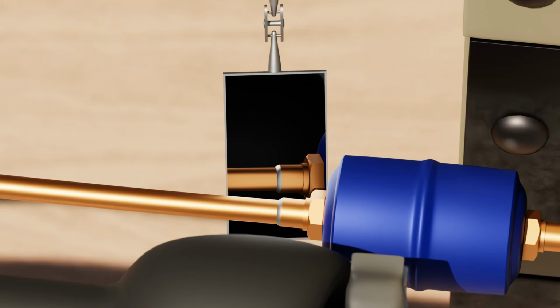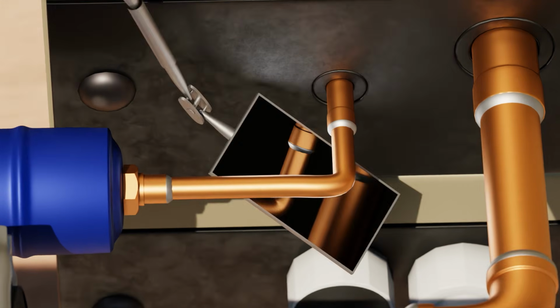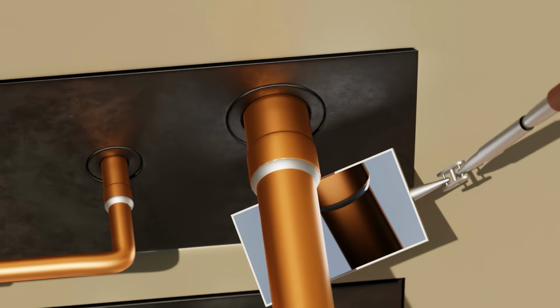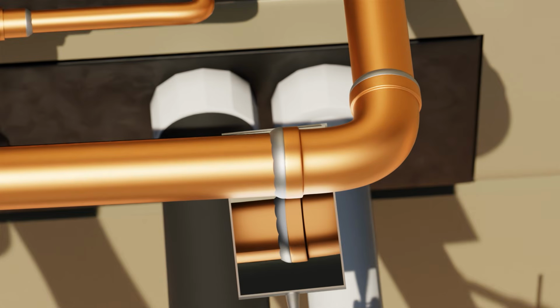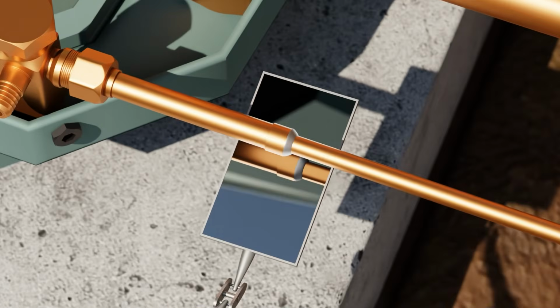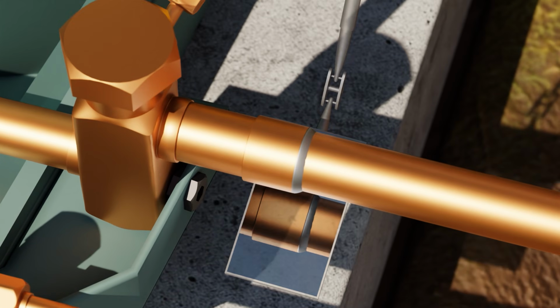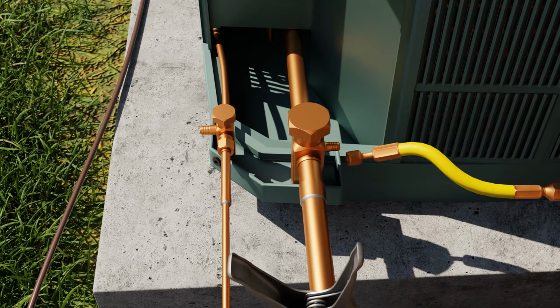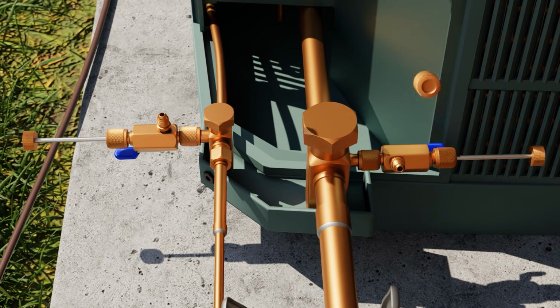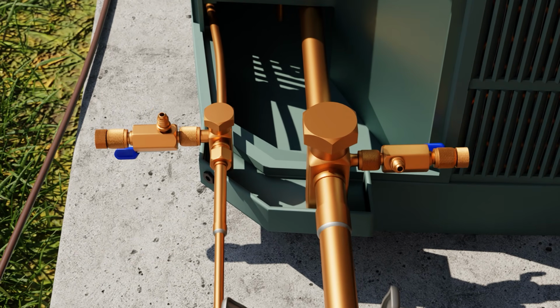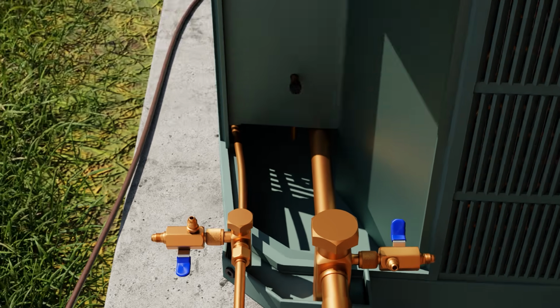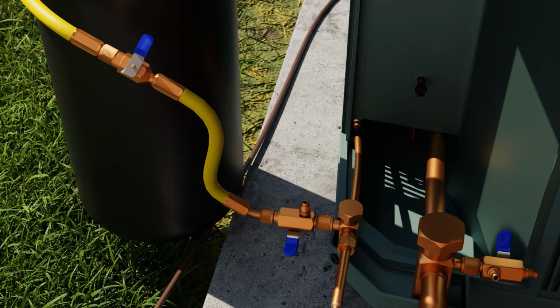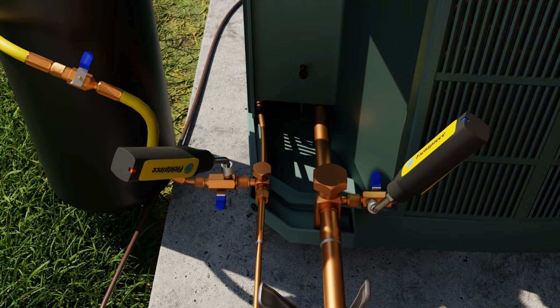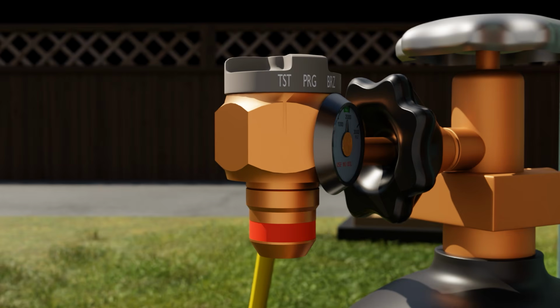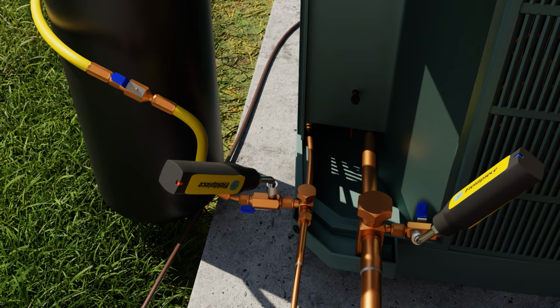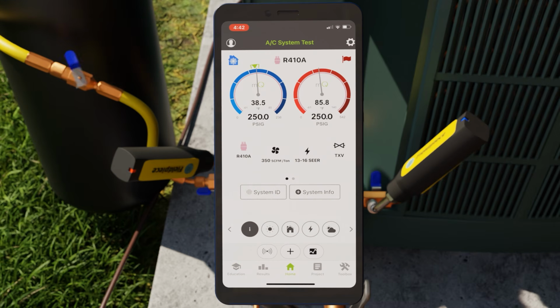Now you're going to inspect each connection with a mirror to make sure they all look as they're supposed to before we move on to our pressure test. Now we're preparing our system for our standing pressure test. You're going to pressurize the system to a fixed number. In this case, we're pressurizing it to 250 psi.